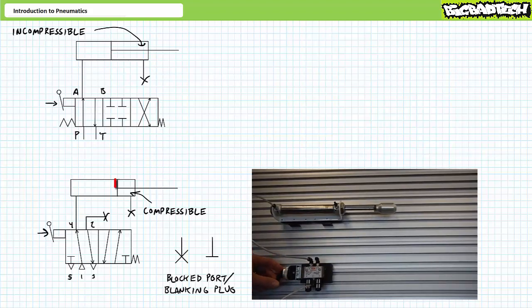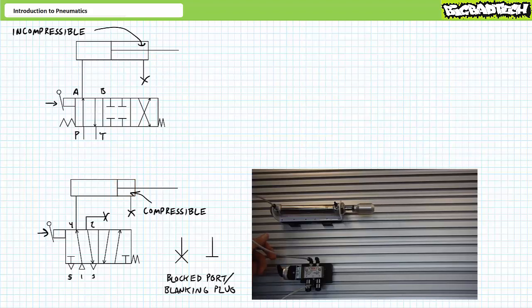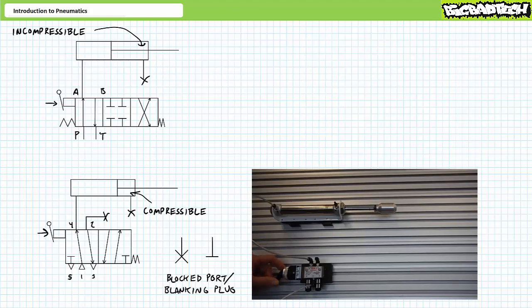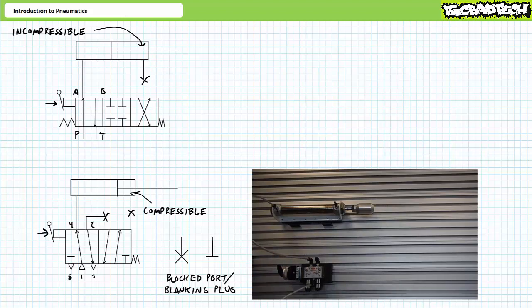Additionally, given all that compressed air in the blocked rod end, consider what happens when the cap is exhausted to atmosphere by shifting back to the retract position. The compressed air trapped in the rod end is free to re-expand and the rod springs back. The point being that the compressible nature of air makes a pneumatic cylinder with a blocked rod end port behave fundamentally differently from a hydraulic cylinder using incompressible oil.